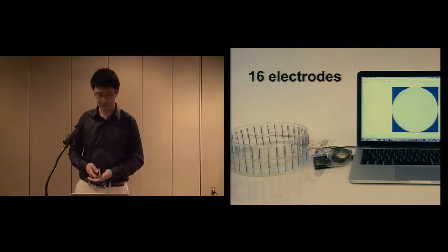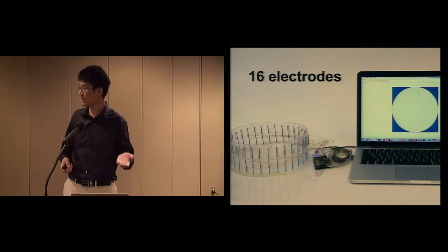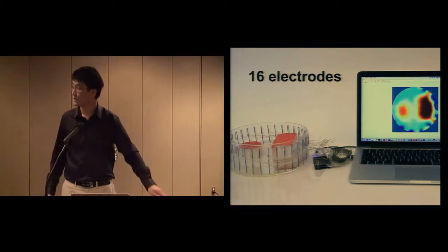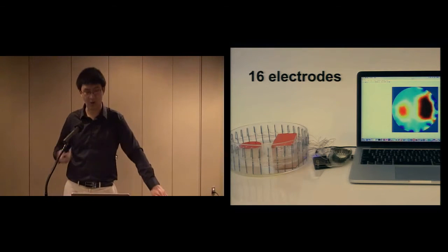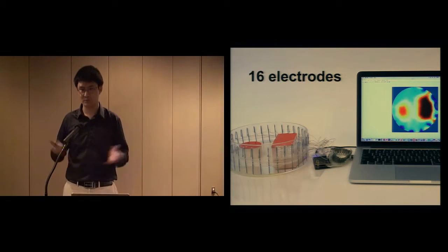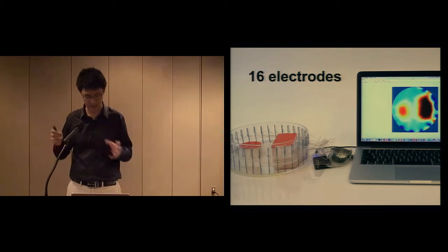To test image reconstruction, we built a saline water tank, as you can see on the left, and dropped objects of known size and shape into that tank. This is a common evaluation strategy with all tomographic systems. These objects here are called phantoms, and computed tomography, MRIs, all sorts of stuff can be tested with this kind of setup.